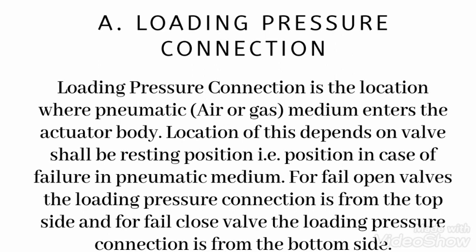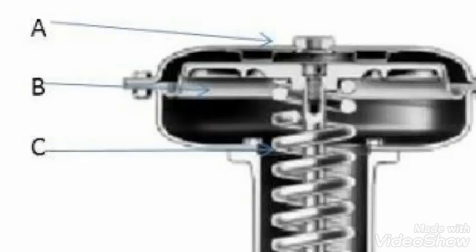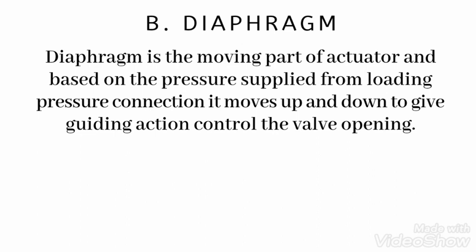The location of the loading pressure connection depends on the valve's resting position in case of failure of the pneumatic medium. For a fail-open valve, the loading pressure connection is from the top. For a fail-closed valve, it is from the bottom side. Here you can see A is the air connection from the top, because this is a fail-open valve — when the air fails, the actuator will open and make the valve open.